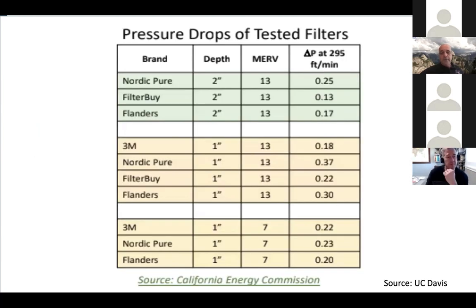So here's a chart based on manufacturer. This is from UC Davis. And you can see that some of the better brands, 3M makes a MERV 13 filter that has a lower pressure drop than some of the MERV 7s. So like I mentioned, if you buy a good quality MERV 13 filter, it won't really impact your equipment. It should function as designed. The only caveat is you have to change these things every 90 days. You have to be a little more diligent with doing your PMs because they capture a lot more material. You have to really be on your maintenance because if you ignore them, they can become problematic.